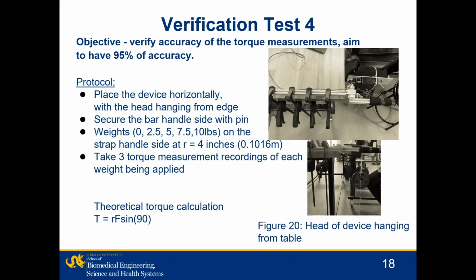In test 4, we verified the accuracy of torque measurement. To get the measurement, we first placed the device horizontally with the head hanging out from the edge of a table. Then we secured the bar handle side with a pin and applied weight on the strap handle side at location R equals 4 inches to measure the torque. For each weight, we took 3 torque measurements and averaged them. The theoretical value is calculated following the equation T equals R times F sin 90 to verify the measurement.